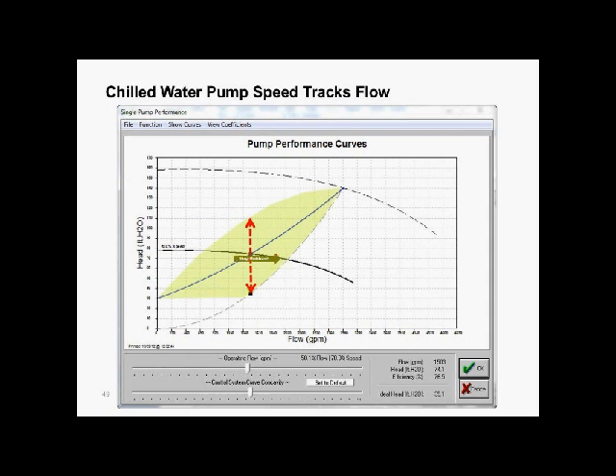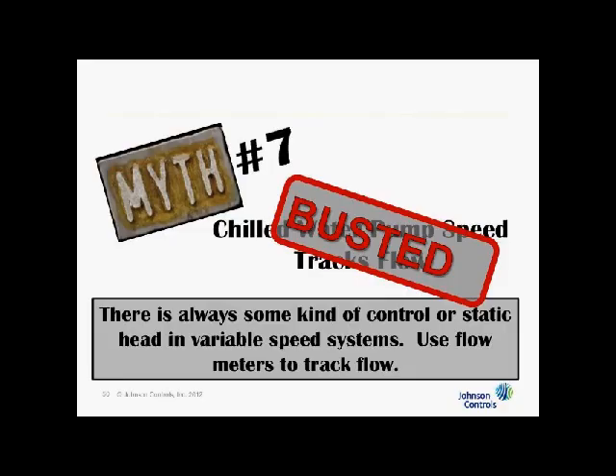So you're actually operating all in this head area all the time. And what you notice is that I could be at this head, or I could be at this head. If I'm at this head, my speed will move down to here. If I'm at this head, my speed will move up to here. So speed for the same exact flow can be infinite. You've got an infinite number of heads, so an infinite number of potential speeds you could be at, all for exactly the same 50% flow. So speed does not track flow in a chilled water system. Okay? So that myth is busted.